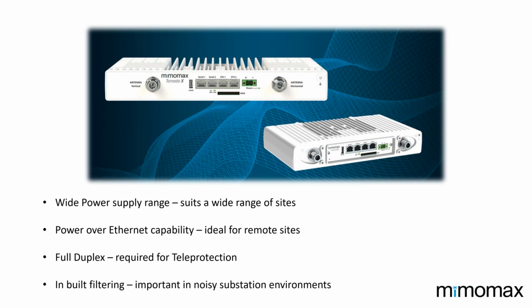We mentioned the full duplex component, and that is a requirement for teleprotection just due to the symmetry. You can't get away with a half duplex or simplex requirement in teleprotection, simply because the asymmetry needs to be well aligned. We do have inbuilt filtering, so the duplexers that are built into the product are bandpass filters. They're relatively narrow, 3 or 4 megs, I think, is the 3 dB bandwidth on that filter. So the skirts rapidly push out to give a 60 dB isolation. So if you are in a noisy environment, you've got a number of competing technologies on a tower, you could be concerned with blocking and the likes. The duplexers in these radios are very good in terms of knocking out potential blockers due to busy and noisy sites.